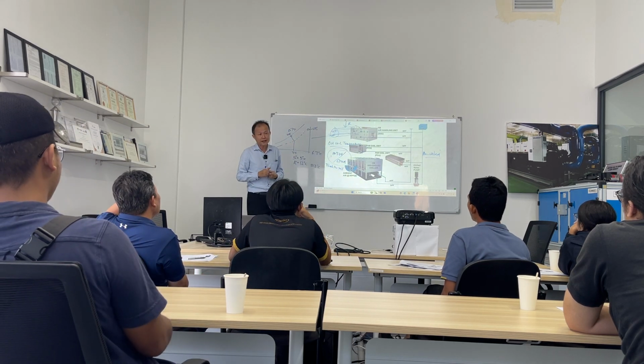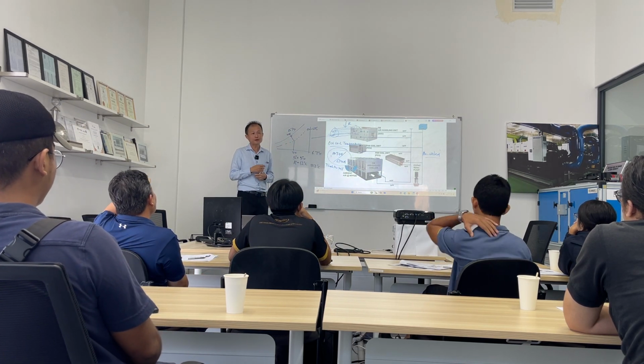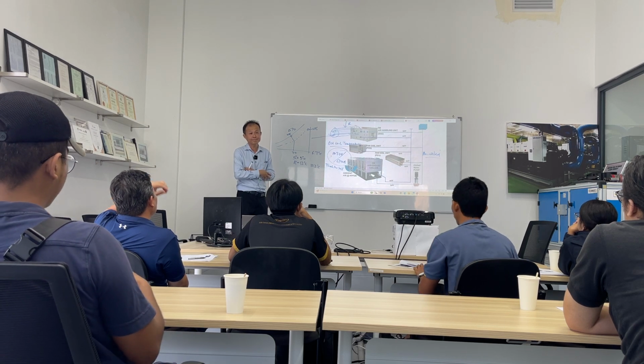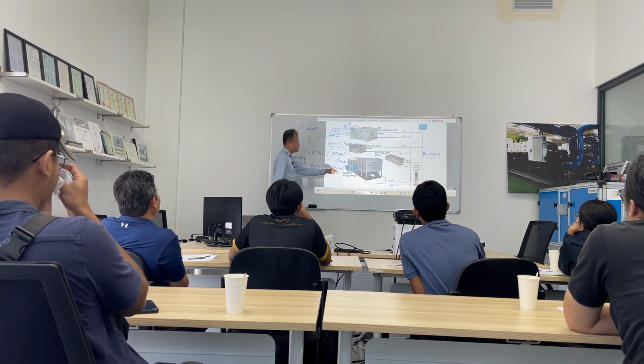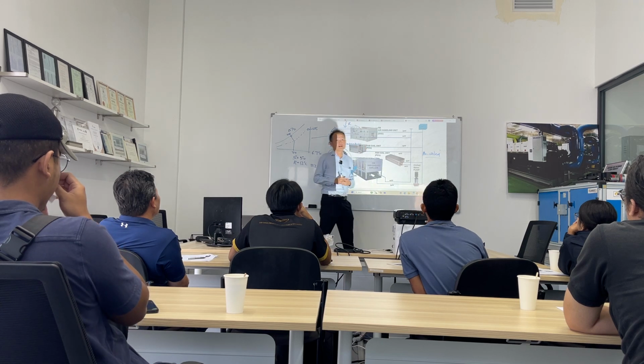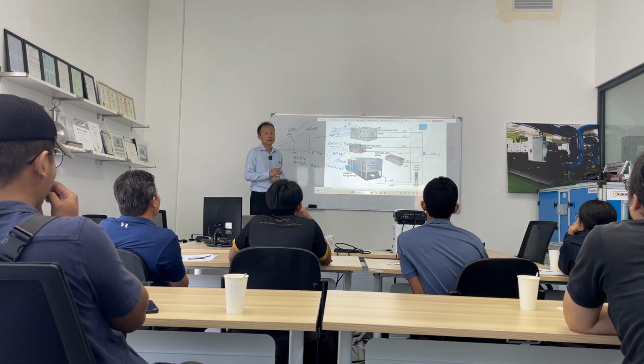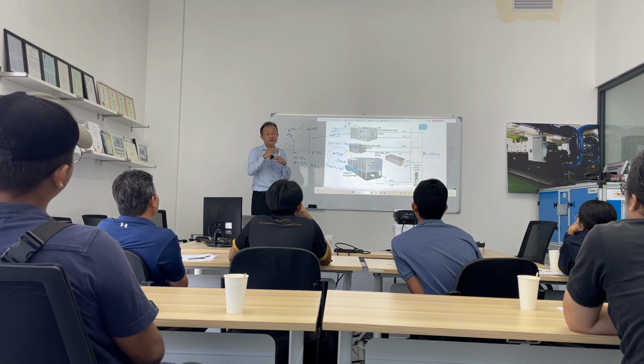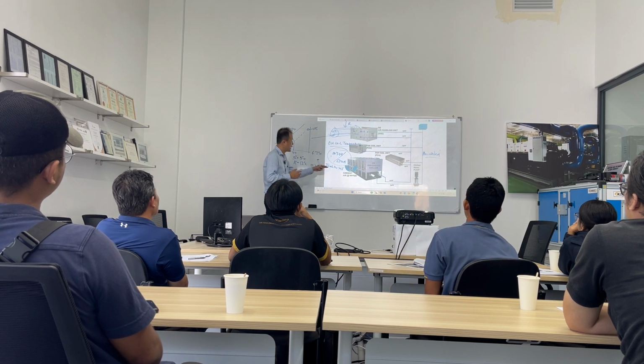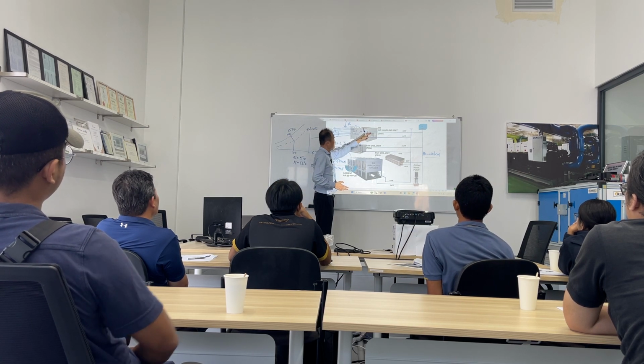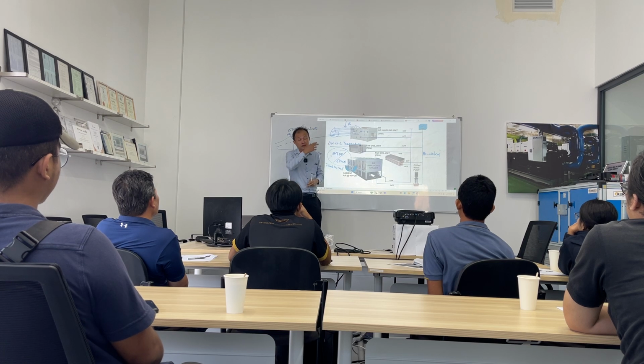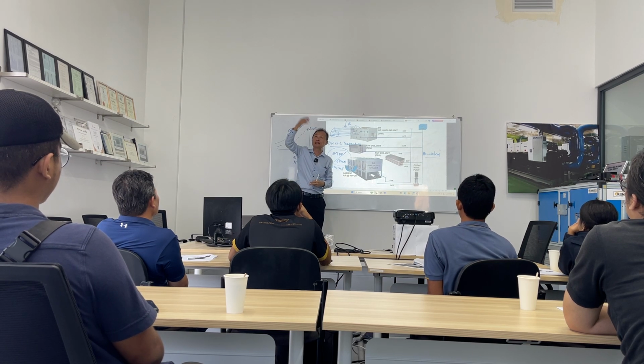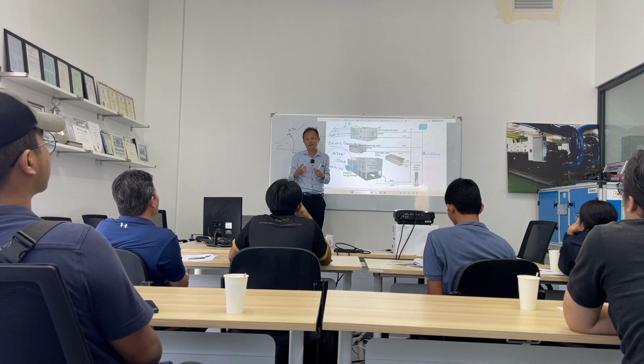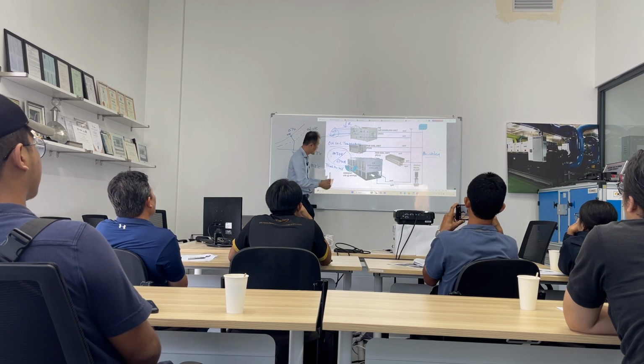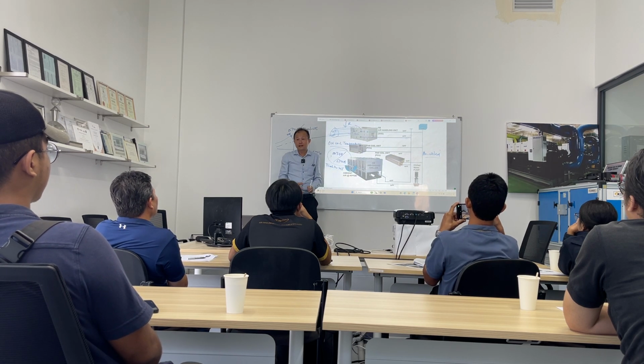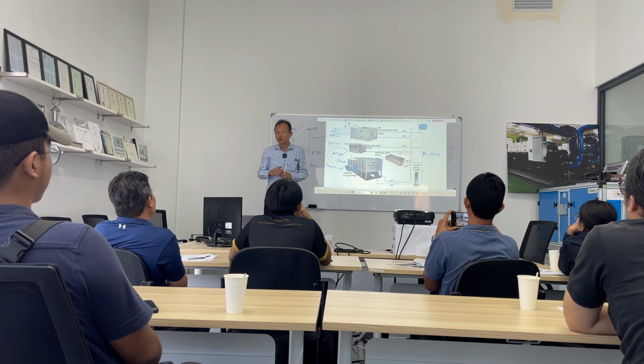Try to memorize this one. You have to, because this is an ARI standard. This is the temperature where we standardize it as an optimum temperature, where it is applied to the AHU or fan coil, it can cool the air very effectively, at the same time without burdening the compressor to work too hard.